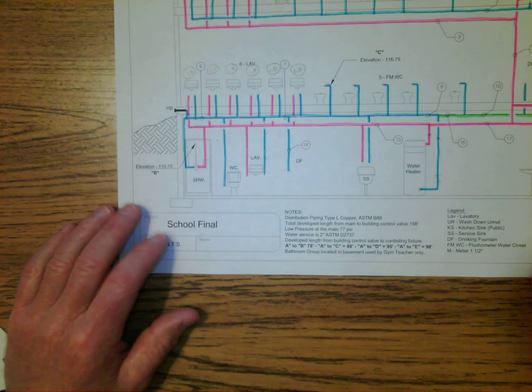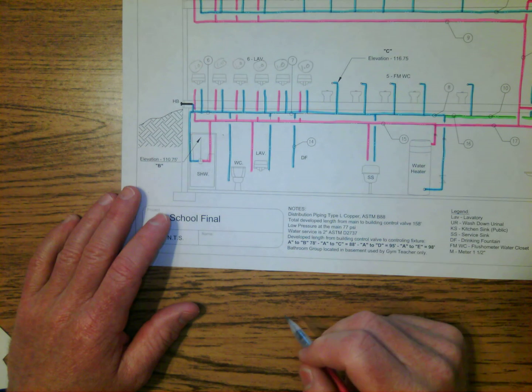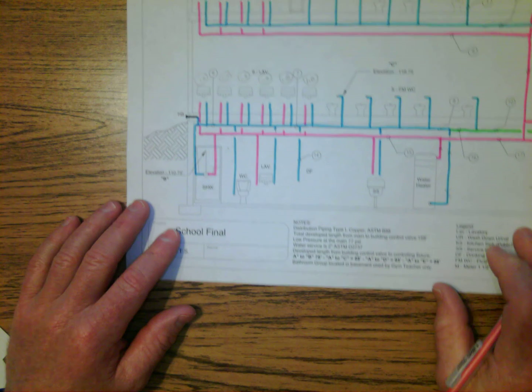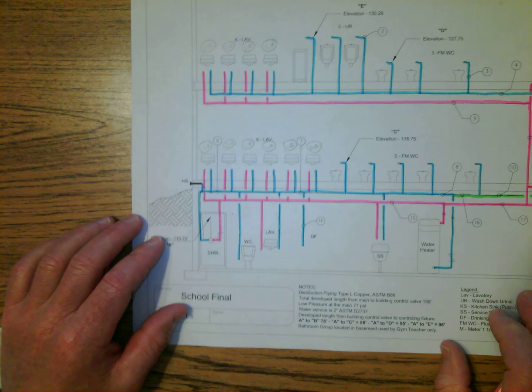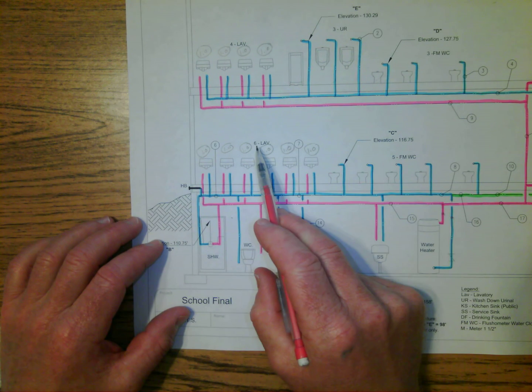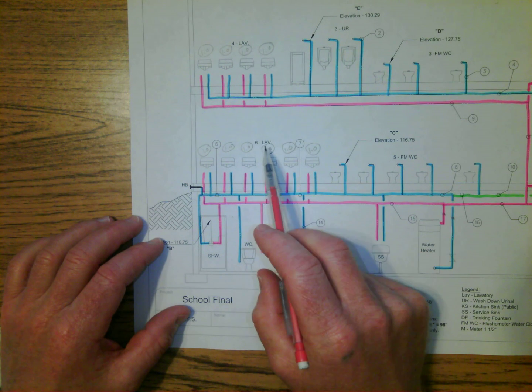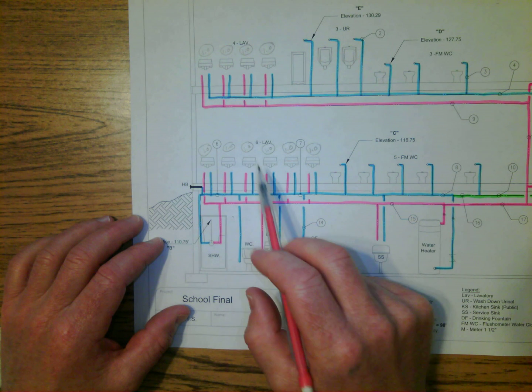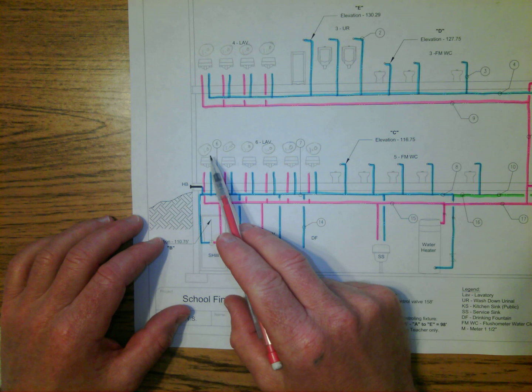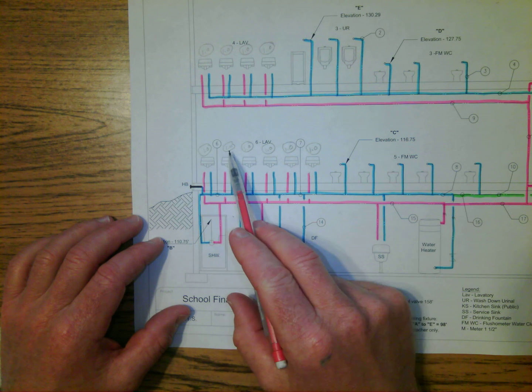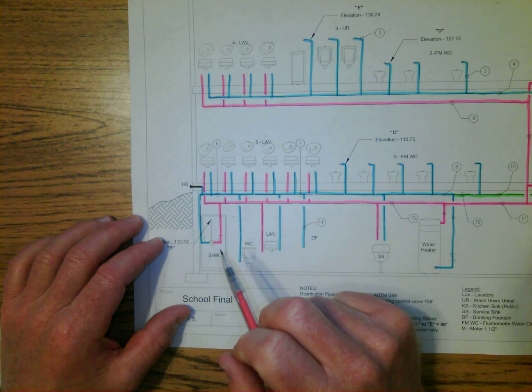So what I'm going to do now is go to the drawing and find lavatory sinks. And here they are. I have 6 of them. And these 6 lavatory sinks, each one of them is worth 1 WSFU. So what I did was assign 1 to each one of them.